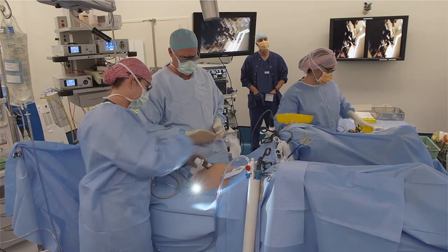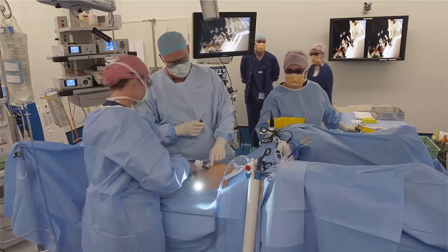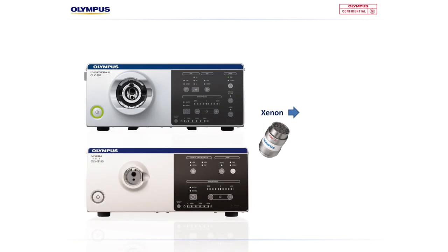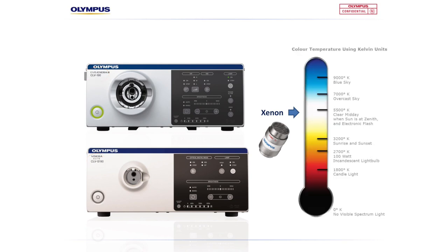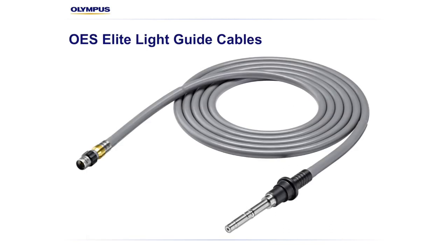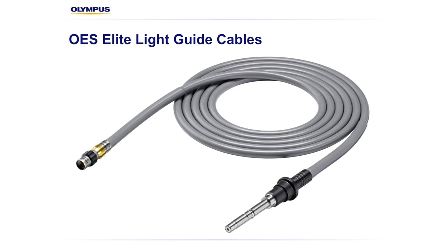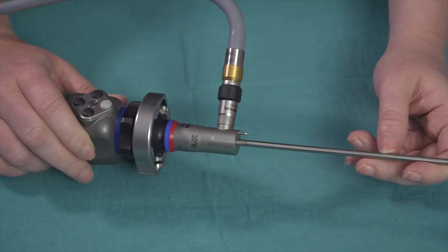We need a light source in order to view delicate tissues within bodily cavities. At Olympus Surgical we use a xenon bulb within a light source unit, typically labelled CLV for platform or generations such as 180 and 190. Olympus utilises xenon light because it's as close as possible to bright natural sunlight, unlike other light sources which can have a yellowy or blue tinge. These light guides are filled with around 40,000 tiny glass fibres, each carrying xenon light from the light source into the scope.